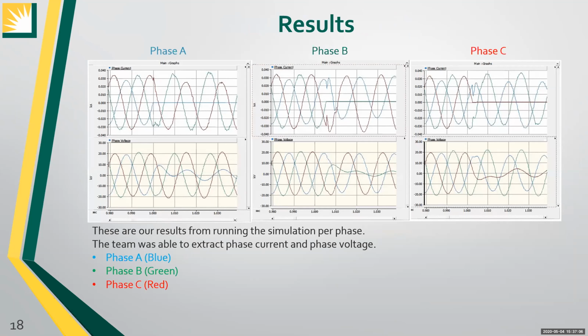After analyzing these graphs, we can visually see that when an open conductor occurs, there is an obvious effect to the remaining two phases. The other two phases begin to fluctuate abnormally for a moment to compensate and balance the load among the two remaining phases. Not only is there a change in load being distributed to the two phases, there is also a phase shift, meaning the waveforms of each phase will shift horizontally on the x-axis, which is the time domain labeled in seconds. After collecting this data, we can give numerical values to the relay team so they can come up with nominal values to program the protection relay. Next, Matthew will explain how the relay team was able to perform this part of the project.